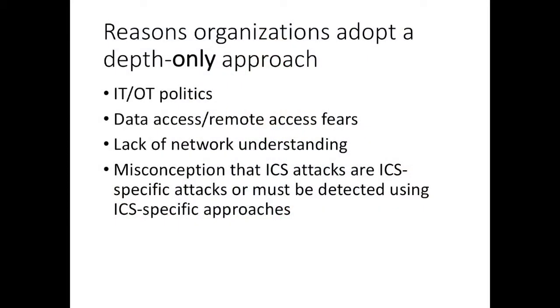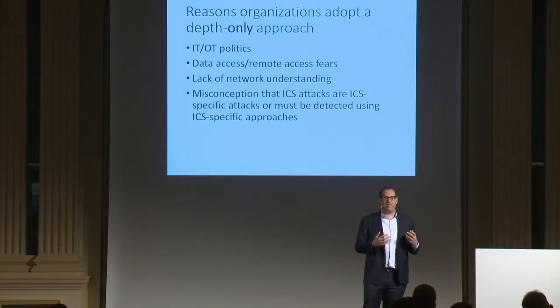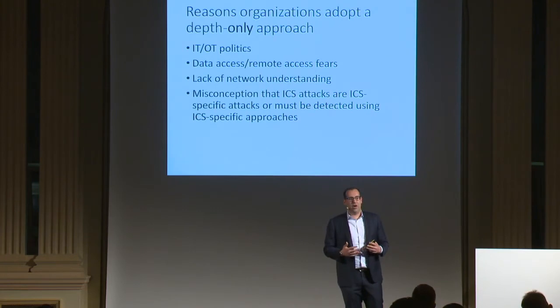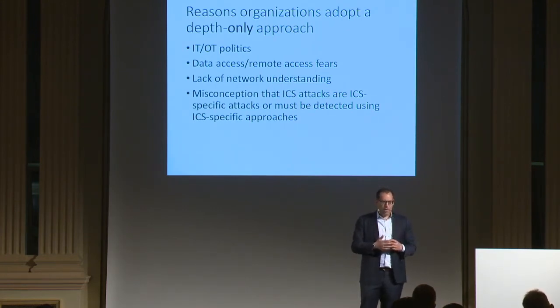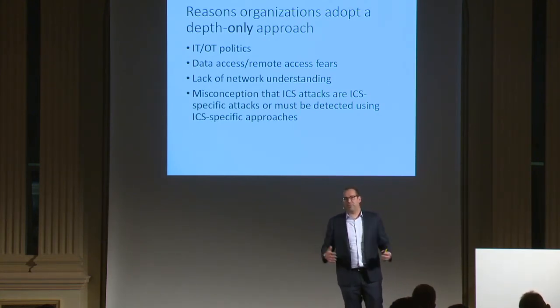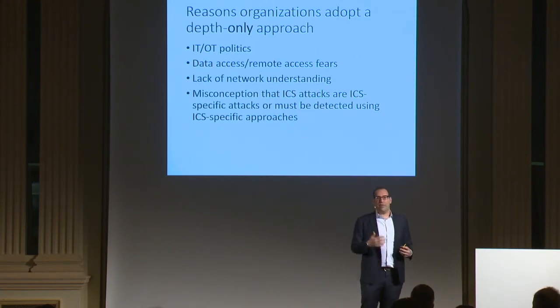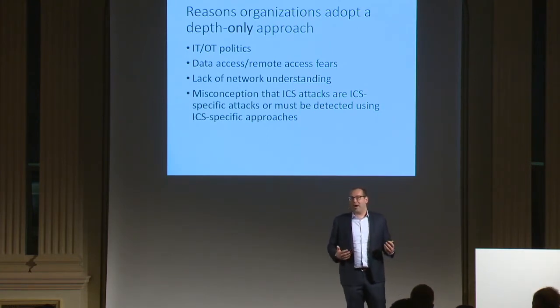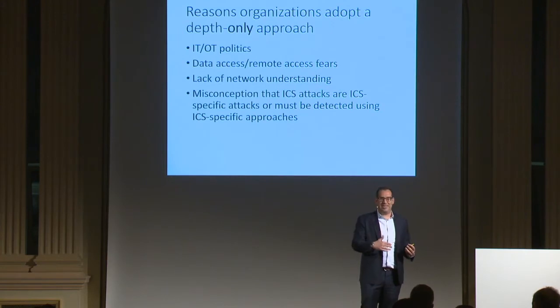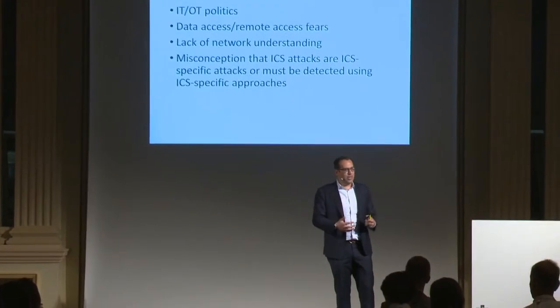Another misconception is that ICS attacks are always ICS-specific. At a chemical facility, an engineer was fixated on securing OSI-PI communications — identified as a risk in the threat model. As I focused more on the network perimeter, the engineer grew agitated. But by examining the firewall configuration, we found the guest wireless network had a route directly into the DCS network. The real risk was not ICS-specific — it was an IT misconfiguration.